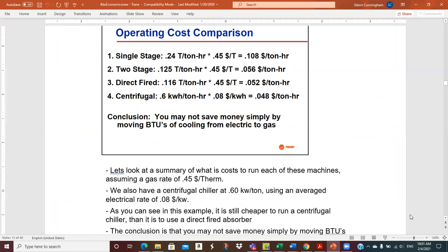I think we may have done this at the end of class before this slide, but basically we just looked at the operating cost to produce a ton hour of refrigeration. Remember, a ton is 12,000 BTUs an hour, so a ton hour is 12,000 BTUs of cooling. We're going to use a gas rate of 45 cents a therm, and a therm is 100,000 BTUs, so 10 therms in a million. That's $4.50 a million gas, which is the way we usually talk about gas cost.